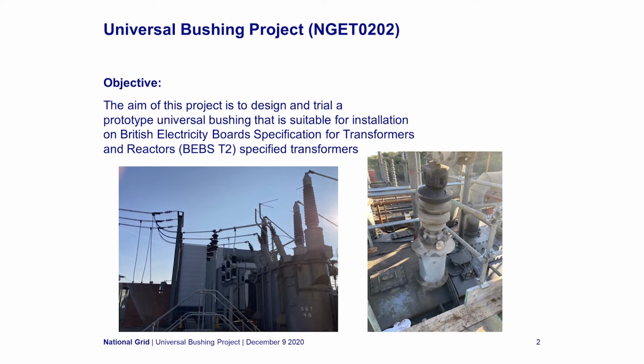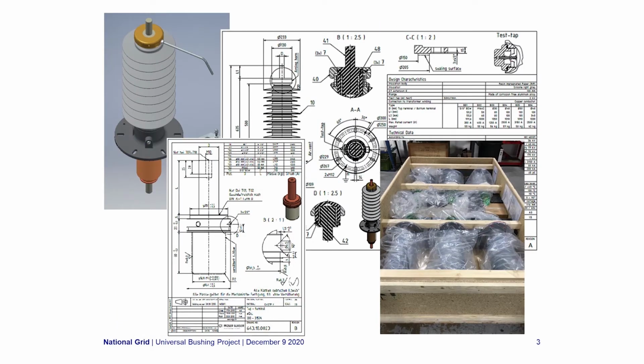You can see here on the left an example of a transformer with 33 kV terminations, and here on the right a closer look at a conventional 33 kV bushing, one that is porcelain clad and oil filled. So for this project, National Grid engineers set about developing a solution that could not only reduce our spares holding, but might also make installation jobs easier, and by meeting modern standards for bushings, reduce risks in operation. The risks are reduced because the oil was removed and the porcelain cladding was replaced by silicone rubber.